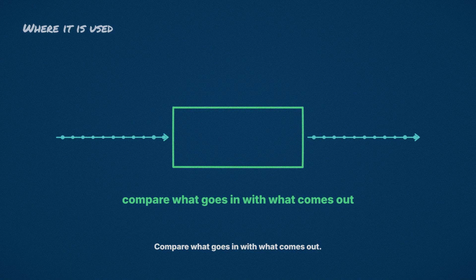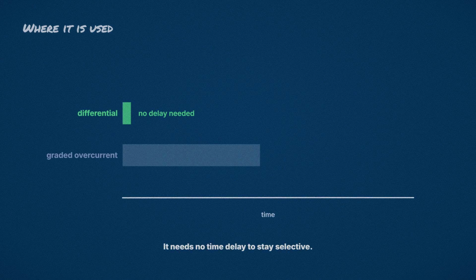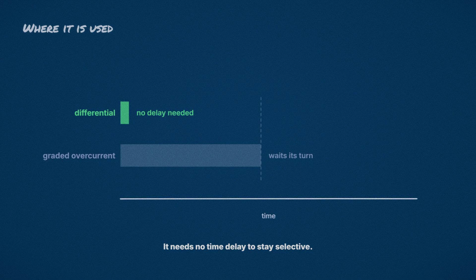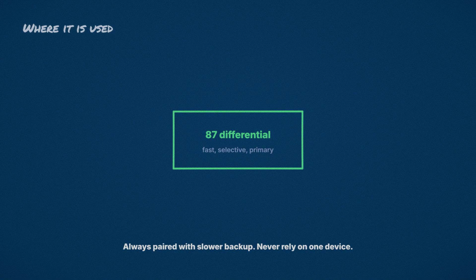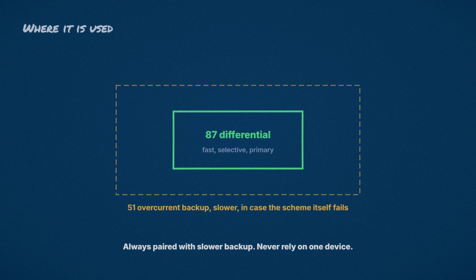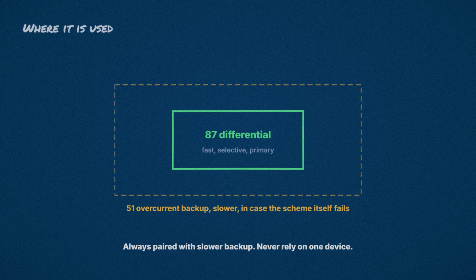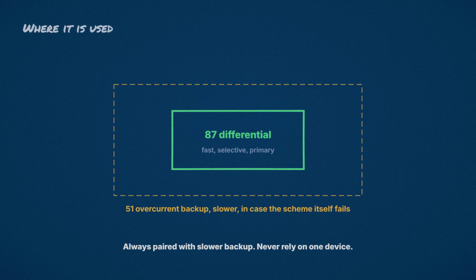Because it acts only for faults inside its own zone, it needs no time delay to stay selective. That is what makes it both fast and precise. It is always paired with slower backup protection, usually overcurrent, in case the differential scheme itself fails. Protection engineers never rely on one device.